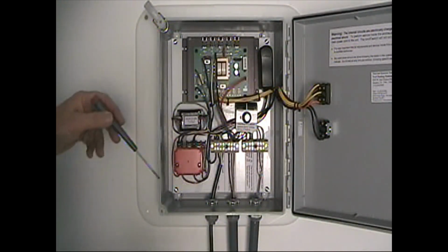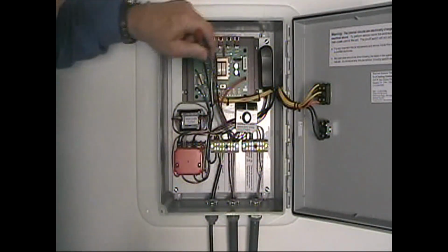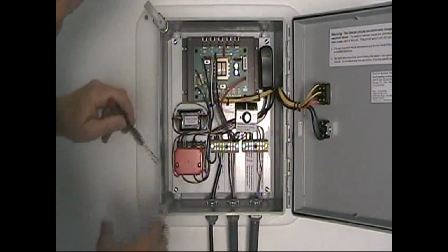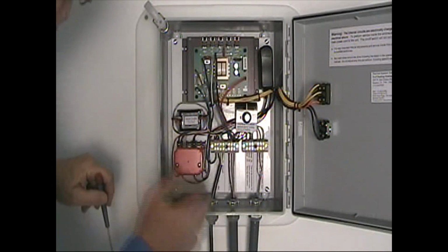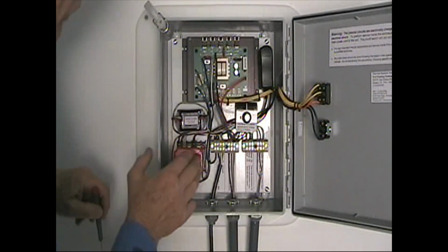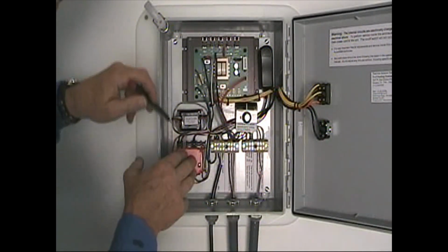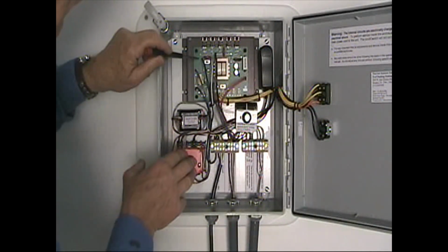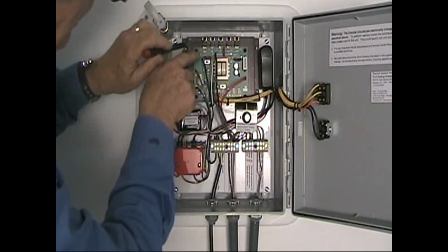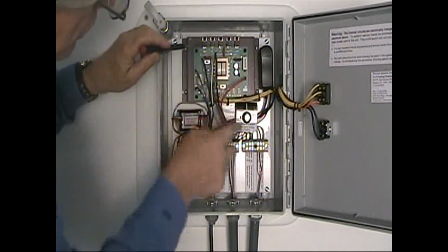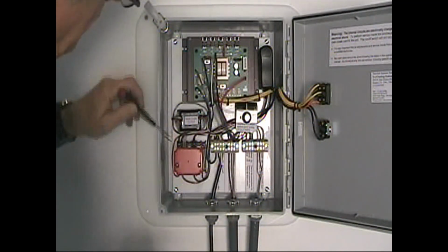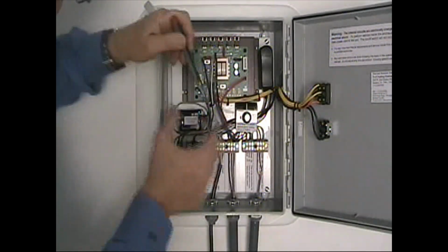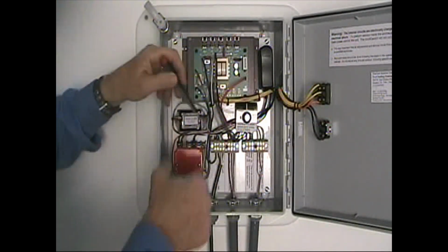While we have this display up, I'm going to show you the different components. This is the SCR drive, the DC drive. This is the analog converter, which takes the flow sensor pulse and converts it from a pulse to a voltage that controls the SCR. The SCR then sends the converted AC into DC voltage out to your motor. This is an optical isolator that protects the interface of the flow sensor with your existing flow sensor on your pump station.